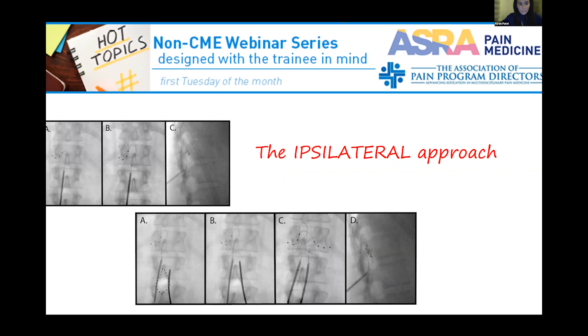You'll see that there is an injection side port there. The only purpose of that is to tell you what direction you are facing. The direction of the side port is the direction of the curvature of the sheath. So when you're steering the sheath, you could take a fluoro and see, but you also have a sense of what direction you are just by looking at the side port. In addition, the way you want it set up, you want a very small amount, probably about 1 to 2 millimeters of the lead exposed at the very tip. You don't want any of the electrodes exposed, but this will ensure that you're not creating a shearing effect as you're moving the sheath out of the foramen.